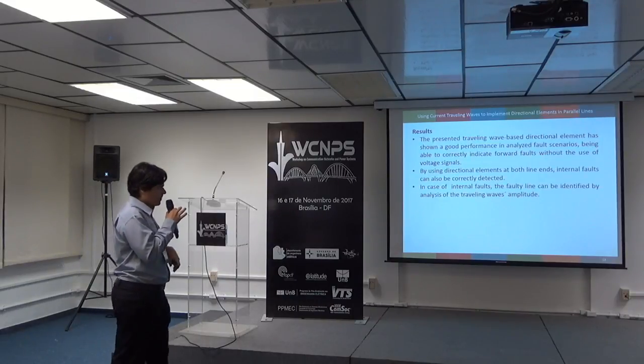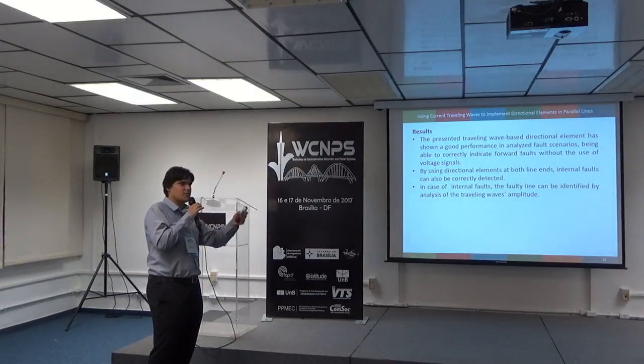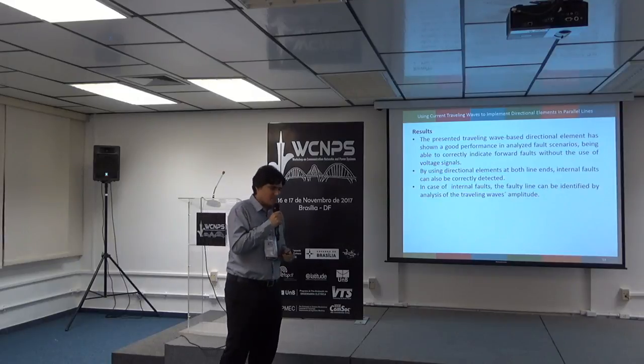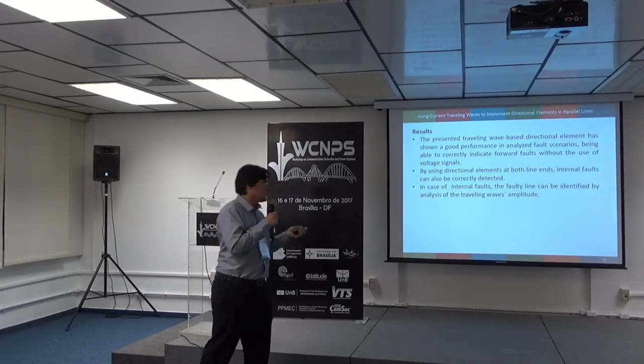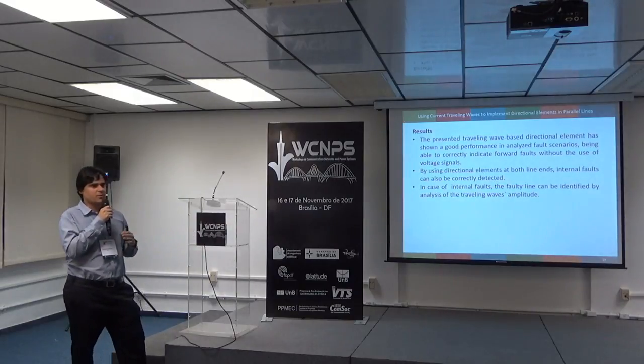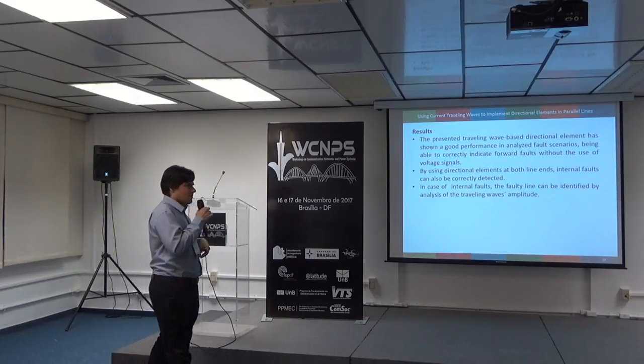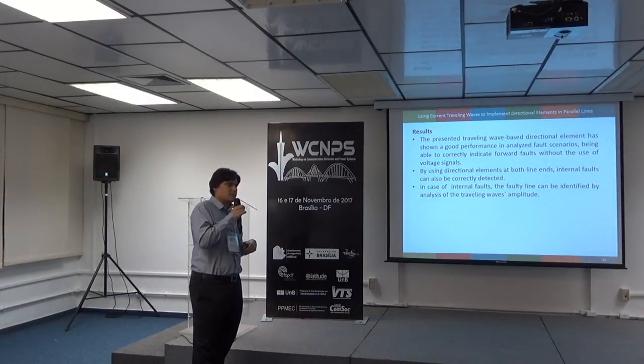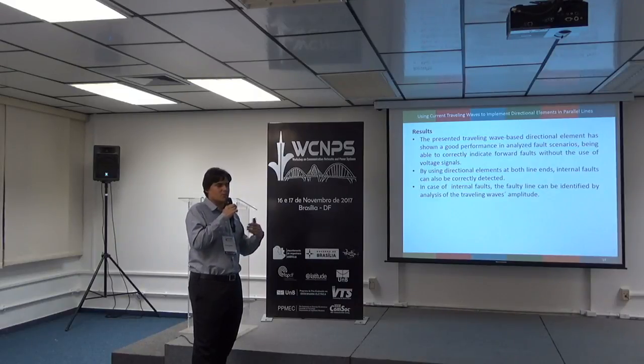In closing, what I said in the first part before the presentation: we use this method to identify the reflected waves in our fault location method. And as we cannot count on the first voltage traveling wave, because the reflected wave will be a second wave, third wave, then to identify correctly the direction of reflected waves, we use this directional element.